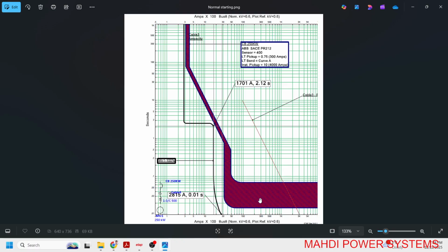During protection coordination, the protective device curve must never cut through the motor starting curve. Otherwise, it trips. In the next video, we'll take the next step and start discussing protection settings.